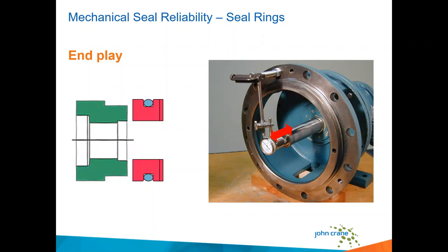to be occurring consistently. If you have some axial movement of the seal, if that's a transient growth or at startup, most mechanical seals can take a certain amount of transient movement. But we don't want, obviously, this situation occurring where the rotor is shuttling or moving axially with every shaft rotation, because we're going to not only have higher leakage, we'll potentially degrade secondary elements, and we'll have a lot of face wear. And so this is important to really understand, again, going back to the installation, that we're starting from a good base and a good foundation in terms of the platform for that seal to be installed in.